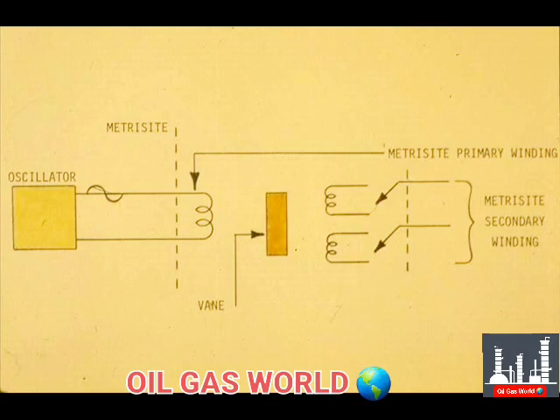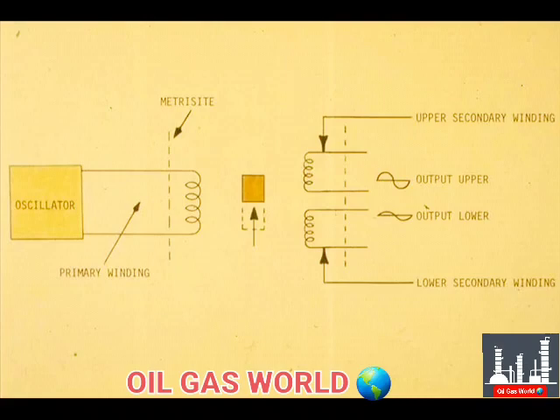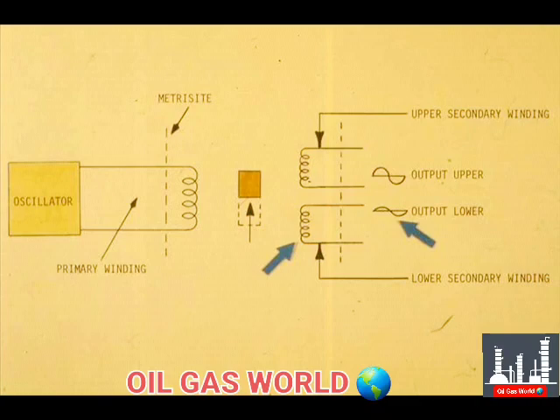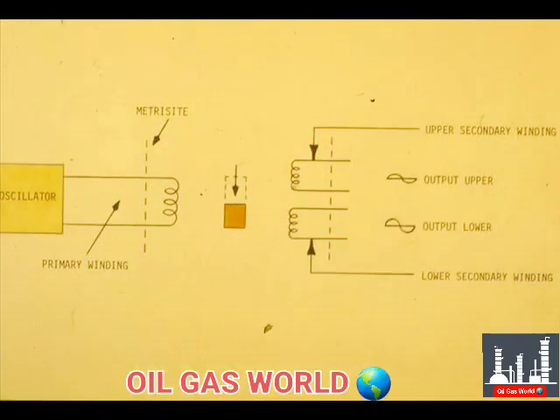This schematic shows the Metrisite and the vane. The Metrisite has a primary winding that is excited by an oscillator. Assume the Metrisite rises. The transformer coupling between the primary and the upper secondary winding increases, so the output voltage of the upper winding increases. The transformer coupling between the primary Metrisite winding and the lower secondary winding decreases, so the output voltage of the lower winding decreases. If the Metrisite vane lowered due to a level change, the output of the upper coil would decrease and the output of the lower coil would increase.